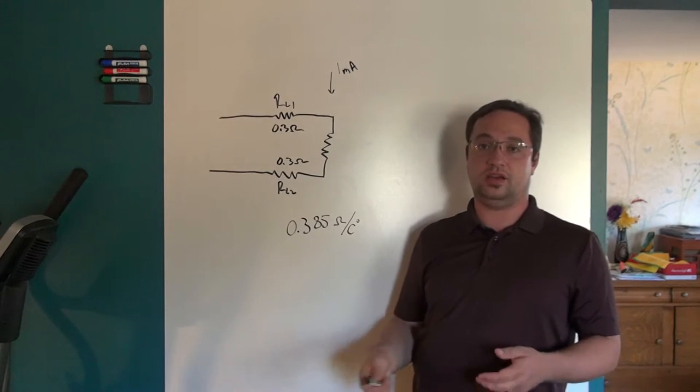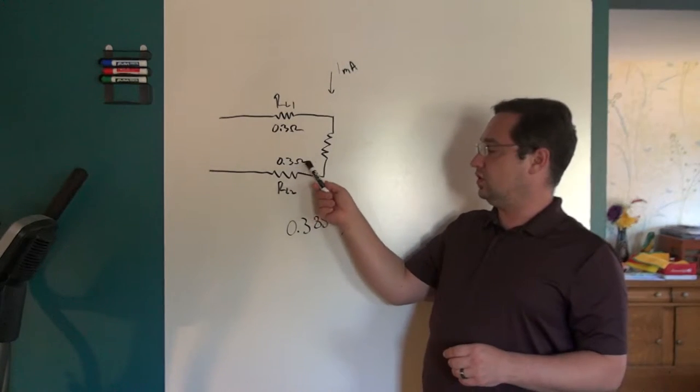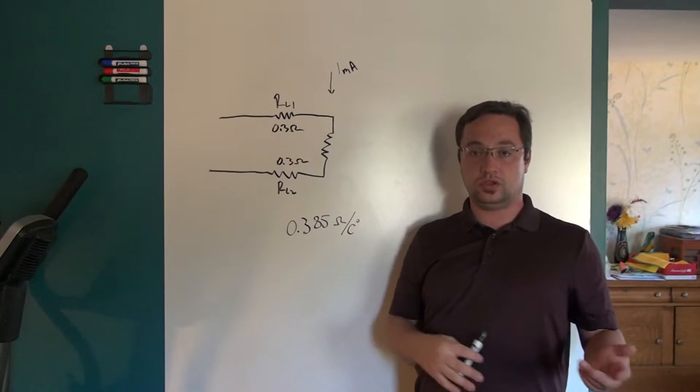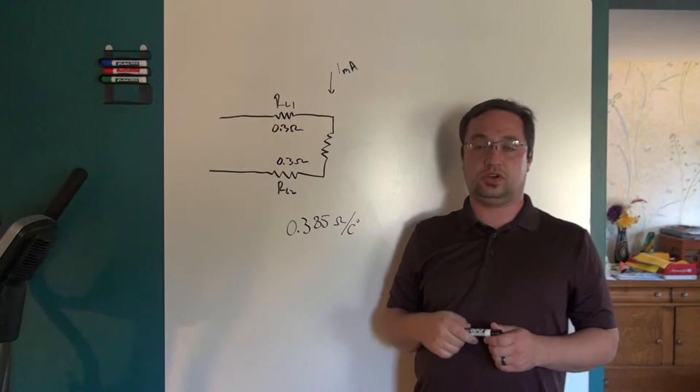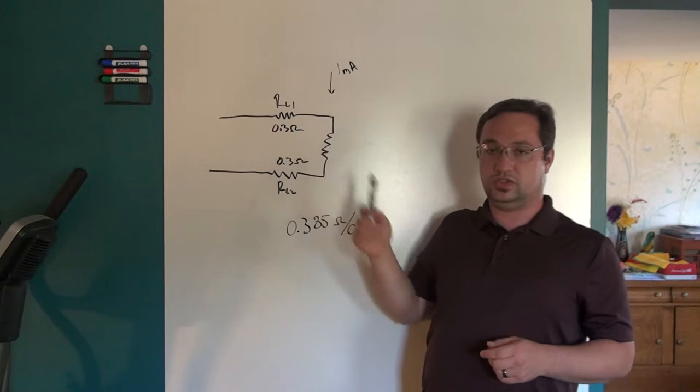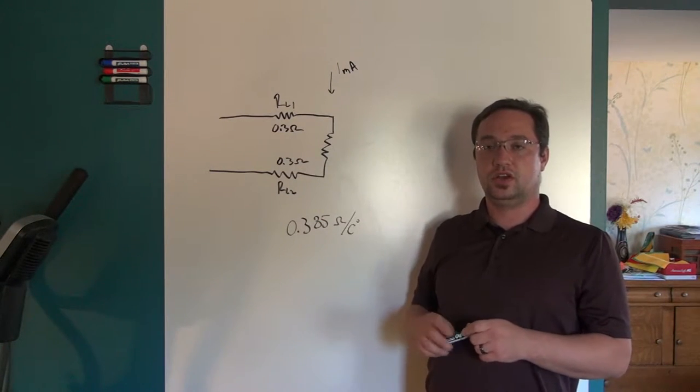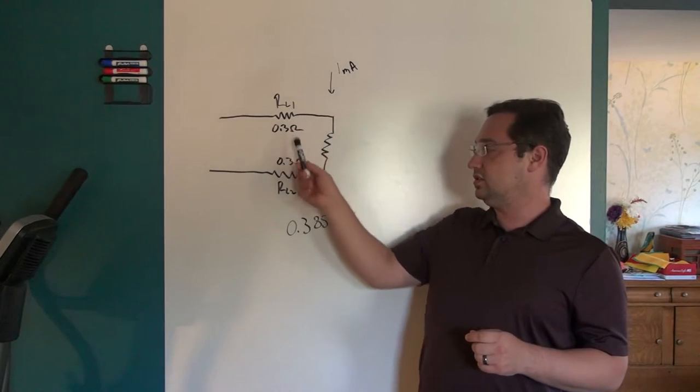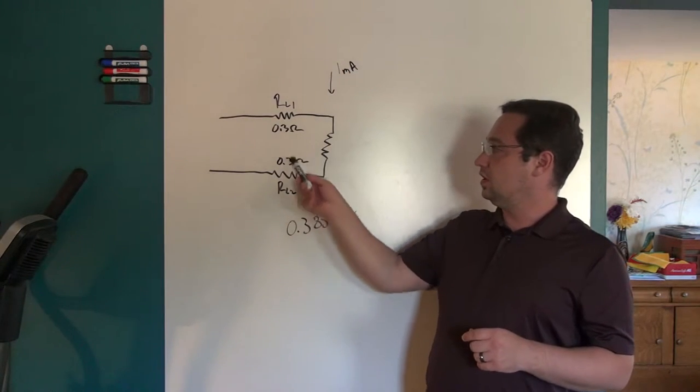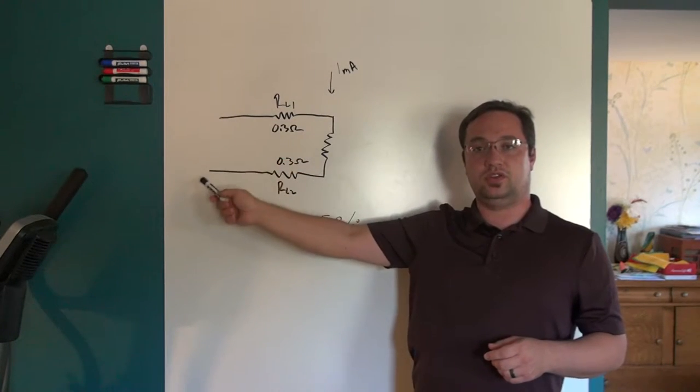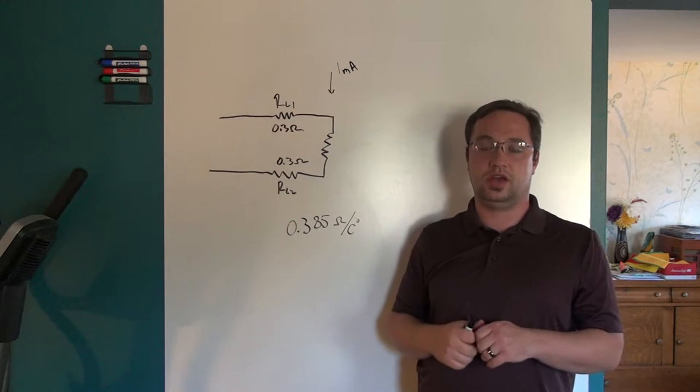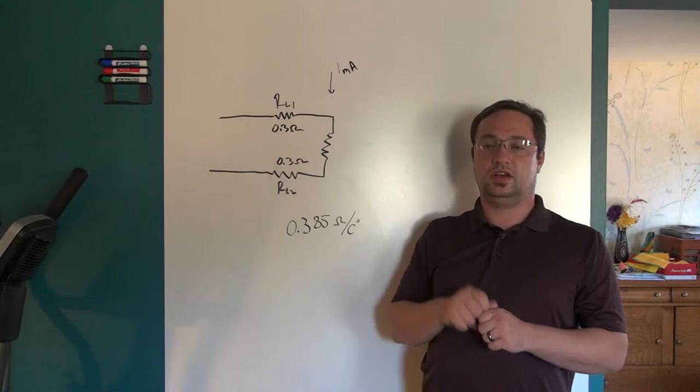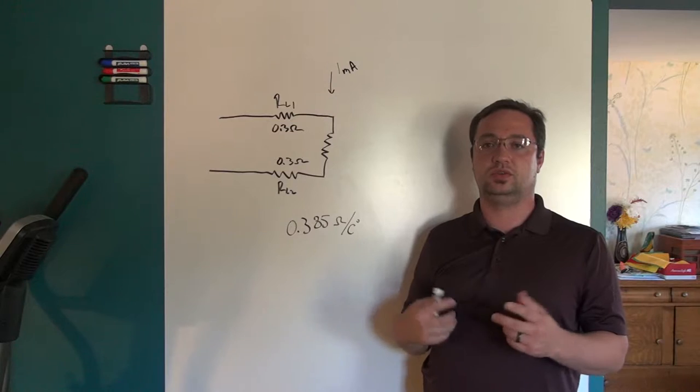So this resistance of the leads will actually also change with temperature. So if you stick the probe into something cold, this resistance might go down. You stick the probe into something hot, this resistance goes up, and now you're actually tracking two separate independent curves because you have a separate temperature coefficient for the platinum and different temperature coefficients for the wires. Also, the leads, the contacts where the sensor actually plugs in, can also change with resistance depending on how good the connection is. Maybe the contacts are just slightly corroded, so now the connection isn't as good.